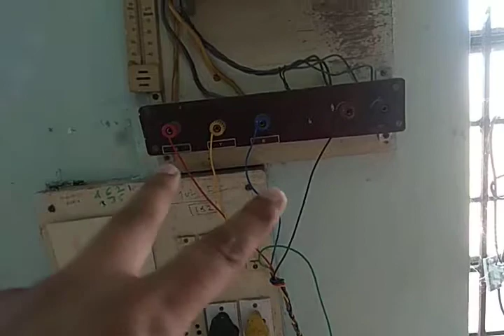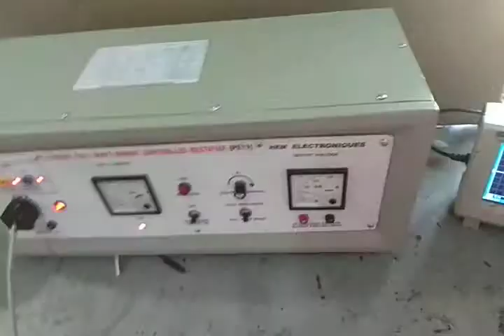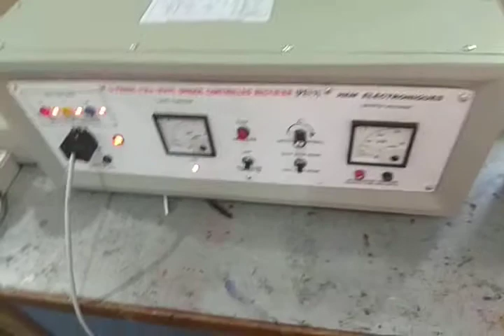So in case you are not getting proper control, you may have to change the phase sequence. Out of these three terminals there are at least 6 different possible combinations, and you just have to swap 2 terminals at a time, like swapping yellow to red and red to yellow. If that doesn't work, swap Y and blue. You have to change the sequence like that until you get proper control. So if the proper sequence is not maintained, you may think the equipment is giving some problem, but there is no problem with the equipment.